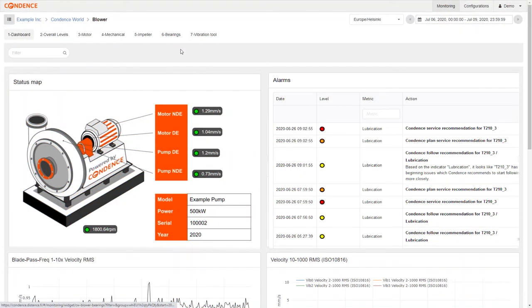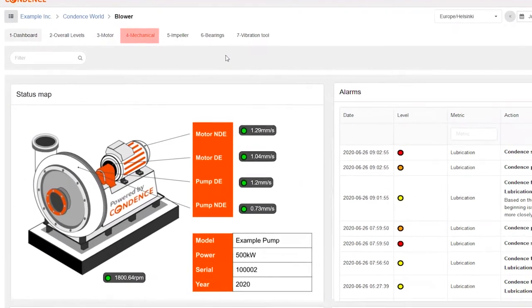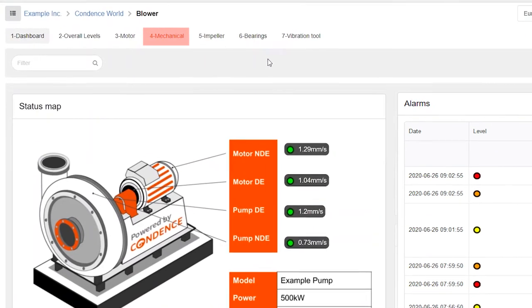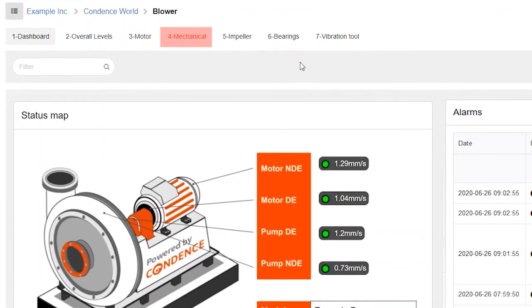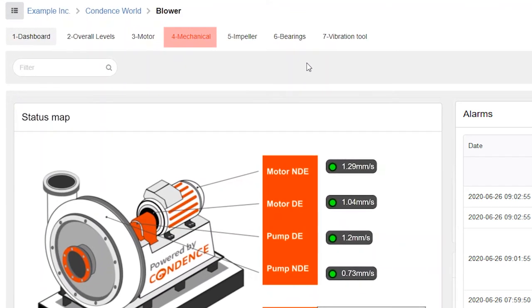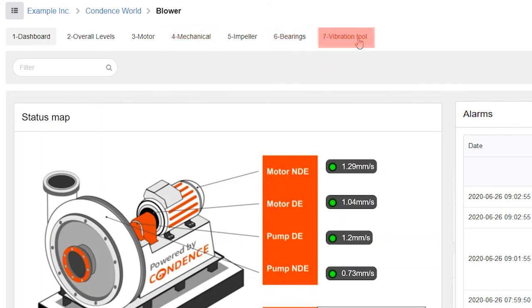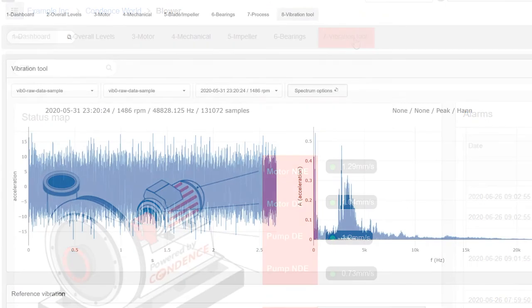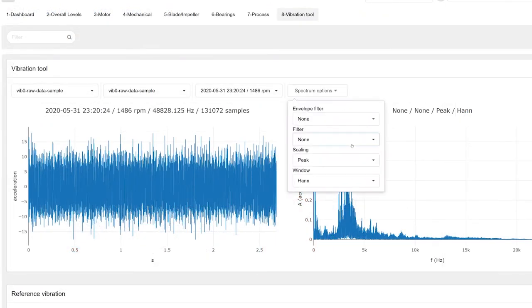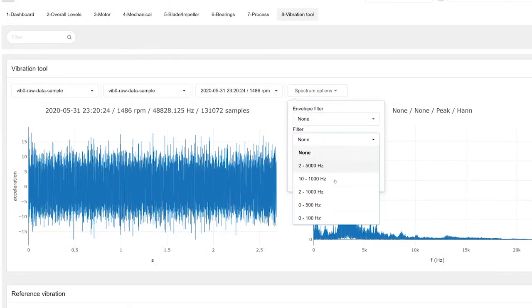In case something abnormal is noted which requires further analysis, a separate page covering that area can be viewed. Let's assume that we've had a notification about unbalance and noted on the front page that something is off. We will dive into more details on the mechanical page to confirm it and see the situation with more information, possibly even check the forecast for that metric. Most likely makes sense to check the bearings and confirm that there is no impact to them as well. In some instances, even manual analysis with vibration tool can be an option.